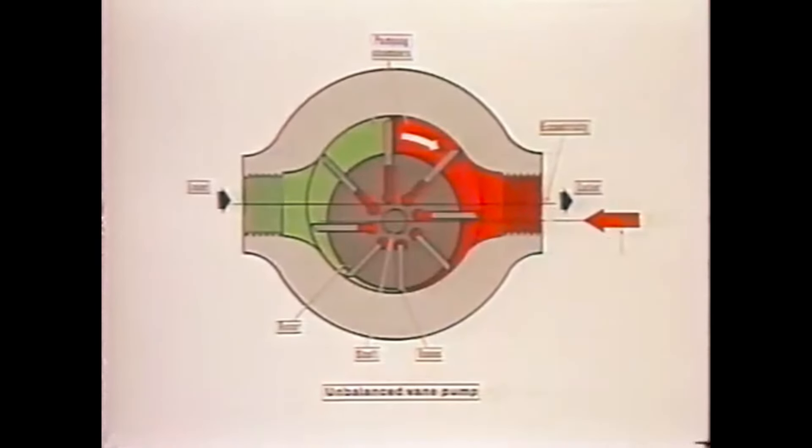This pump has a somewhat limited pressure capability because of its unbalanced hydraulic loading. Its displacement, however, can be varied or even be reduced to zero by moving the ring towards the center line of the rotor.